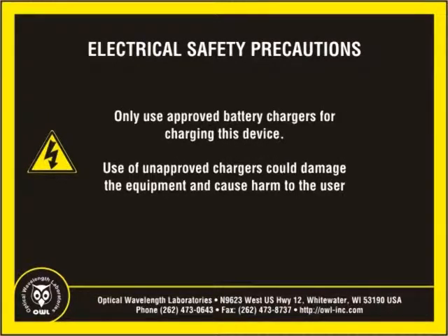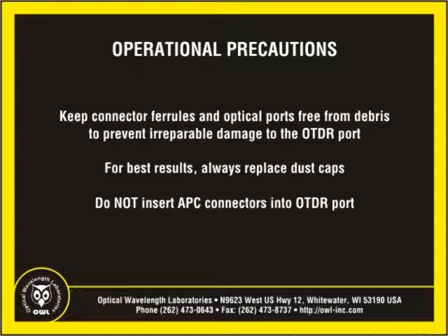Concerning electrical safety, only use approved battery chargers for charging this device. Use of unapproved chargers could cause damage to the device or harm to the user from fire and electrical shock. Keep connector ferrules and optical ports clean to prevent damage to the OTDR port. Failure to properly clean and maintain the OTDR port could cause permanent damage to the internal OTDR optics and could result in costly repairs. For best results, always replace the dust caps after each use and do not insert angled physical contact, or APC, connectors into the OTDR port.